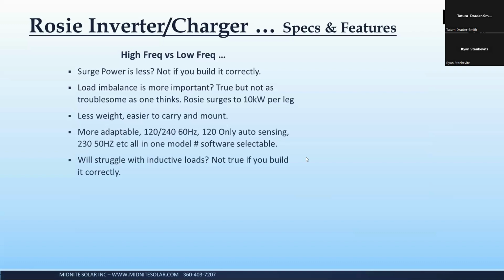And then from 5 to 10 minutes, you can do 125%. And then above 10, above 20, yeah, I just screwed that timing all up. 0 to 5 minutes is unlimited. 5 to 10 minutes is up to 125% of your rating, and above that is 110% indefinitely. So in other words, the Rosie can run at 7,700 watts forever, according to UL, and up to 5 minutes, it can run any number you want to run. Obviously, it's not going to run 20 to 21 kilowatts, or 10 kilowatts per leg, for 5 full minutes. It's going to get hot and it's going to back down or shut off.